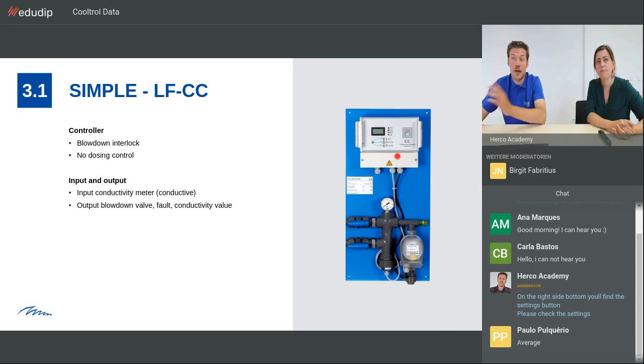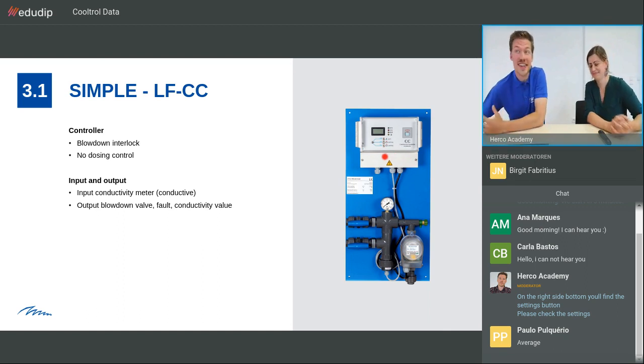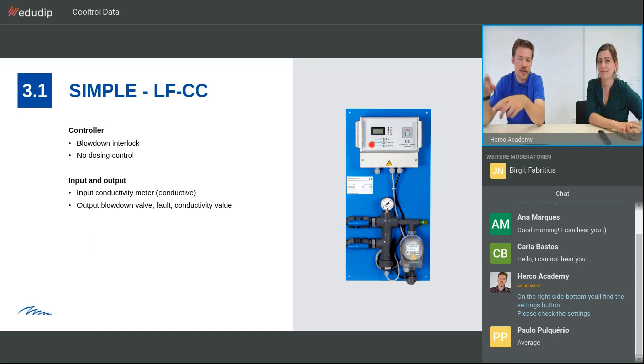Yeah. And I also want to show you something from the technical side. So actually on the controller itself, with the other controllers, you always have buttons where you can set up something in menus, but this one is really, really simple. So you see the red dot, there's just a switch that you can switch up or down for choosing set points and also for calibration, and that's it. So you have basically one switch for all the settings. So this is quite simple. Very simple system. Of course, this is also the most cost-effective system, let's say.